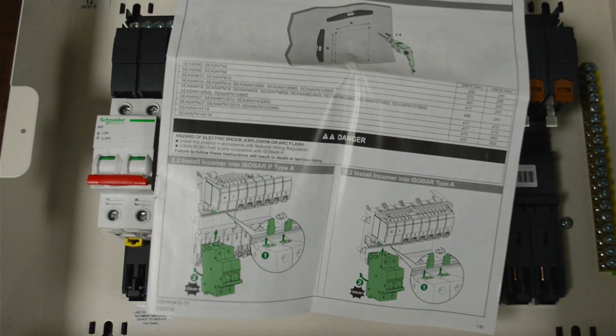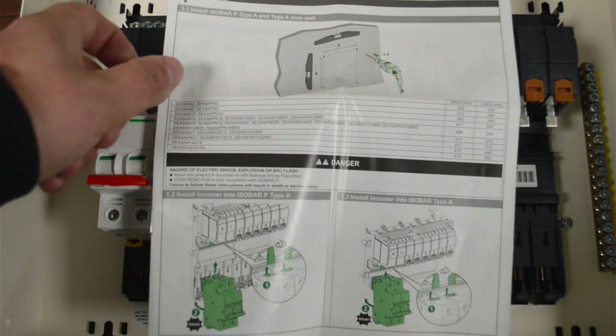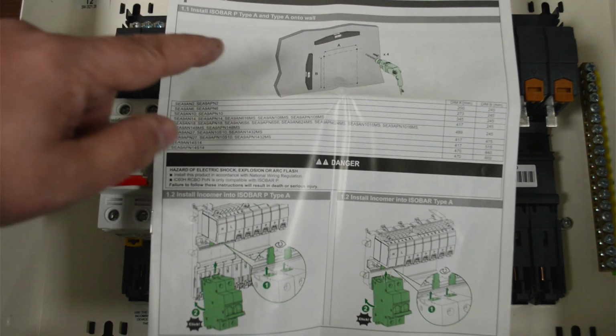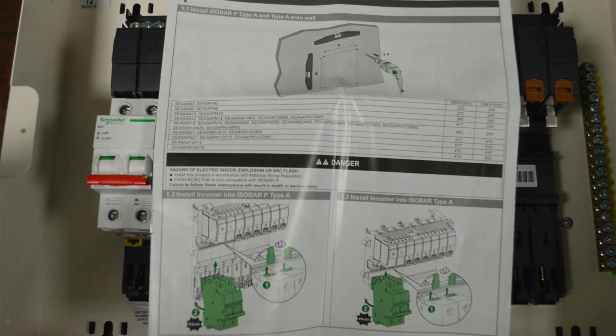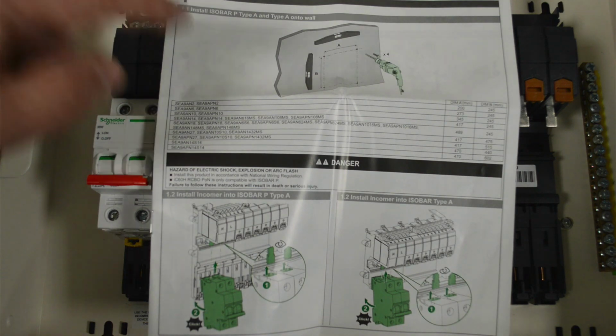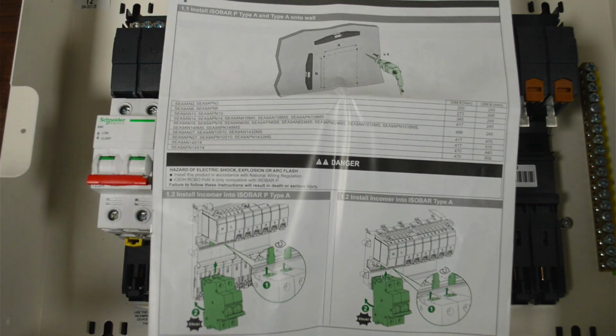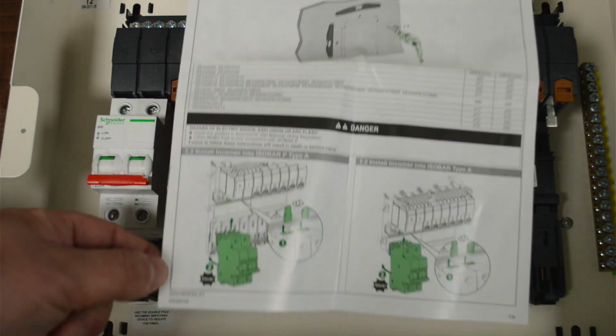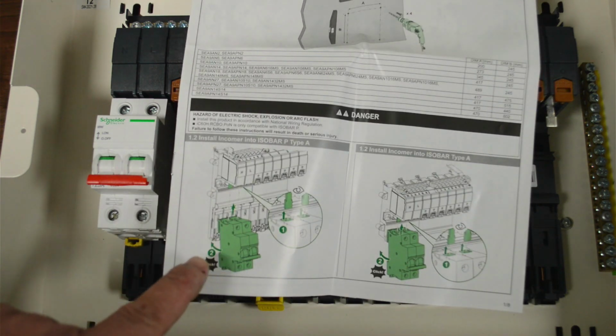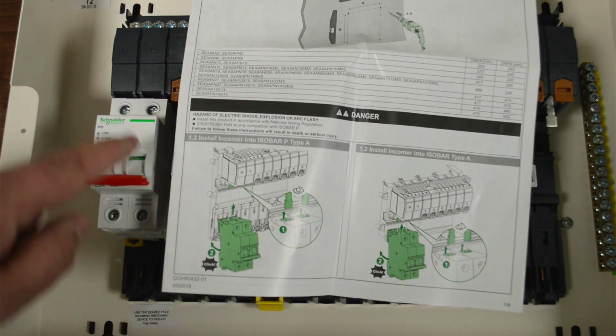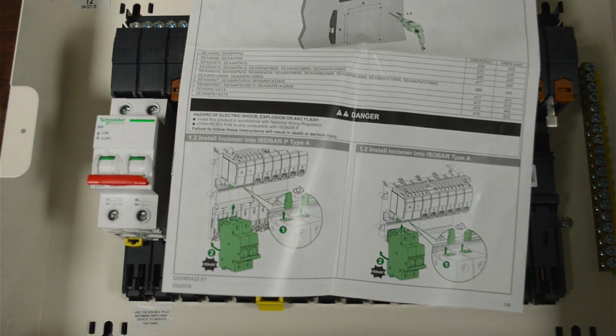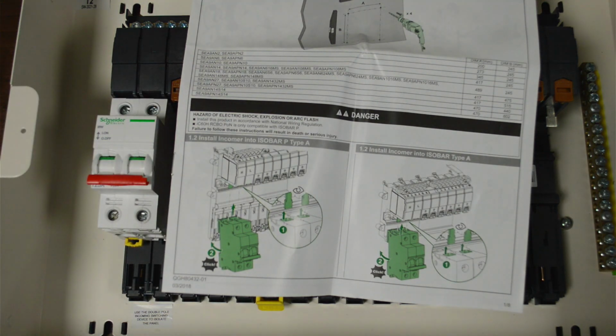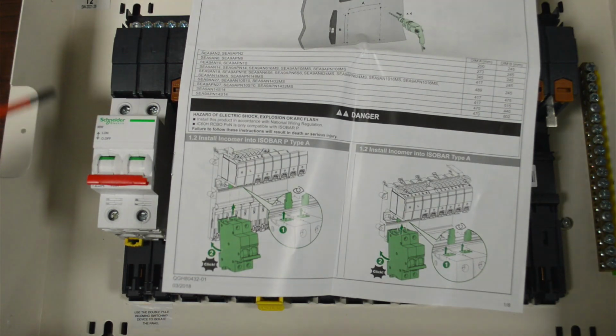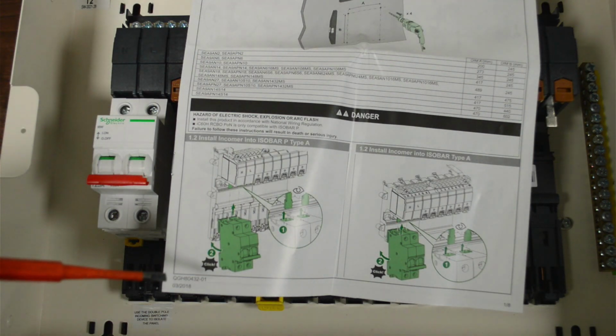So I thought we'd just run through some of the instructions that come with this, and you'll see here it's an Isobar P Type A distribution board, consumer unit, whatever you want to call it, and it tells you the measurements for marking out your holes and ensuring that it's level. It goes through installing the main switch, so you can see there that that actually clips straight onto the line, and the neutral pins, so that actually has a pin underneath it, which the neutral obviously terminates onto, and then you see it going in there.